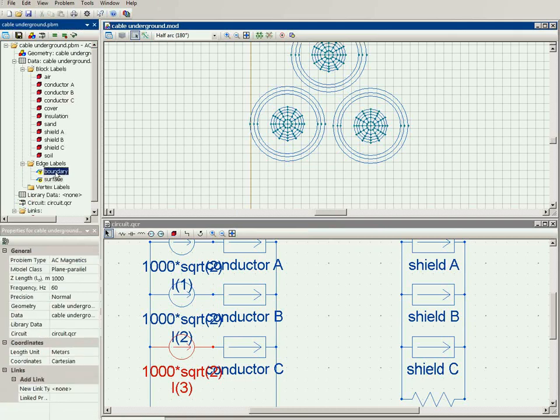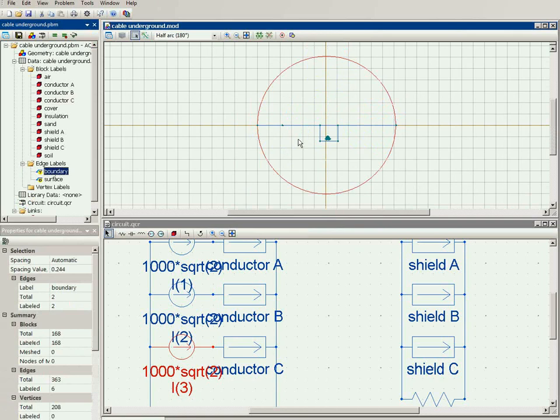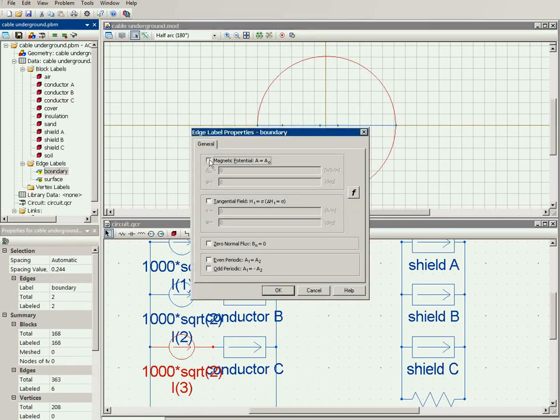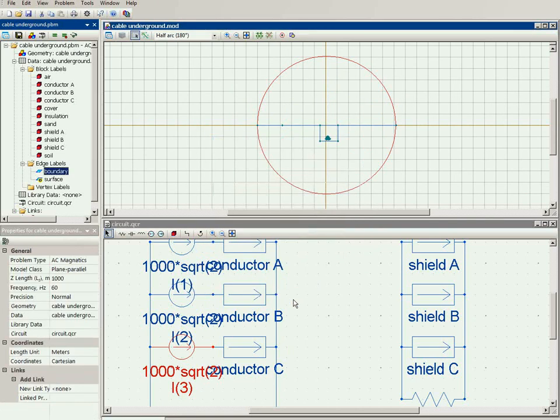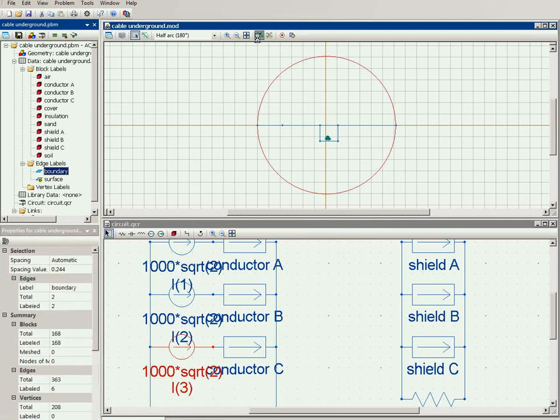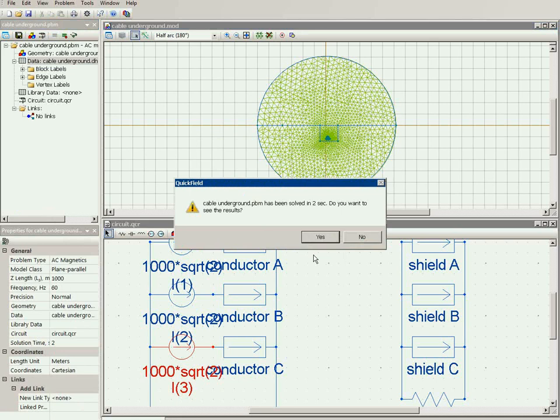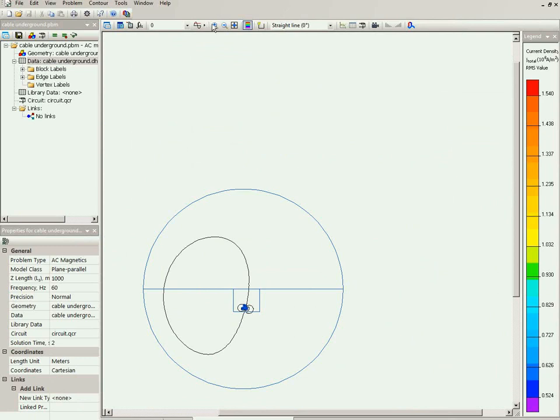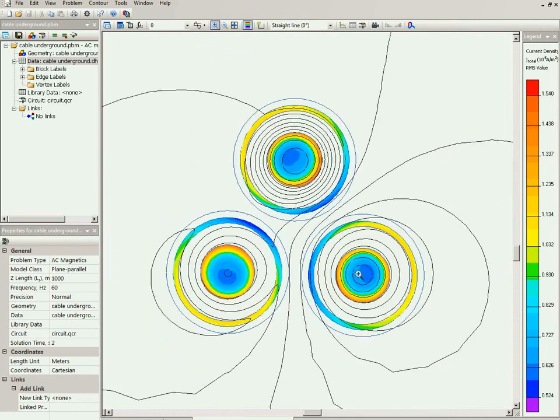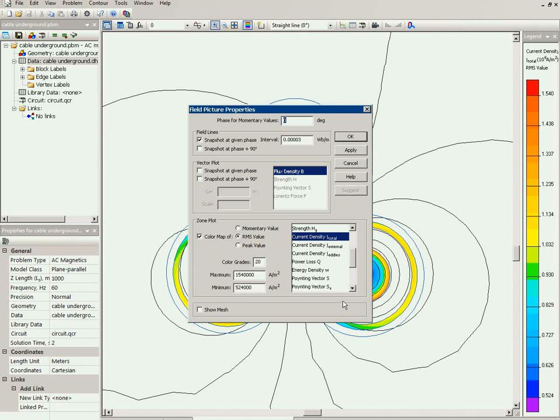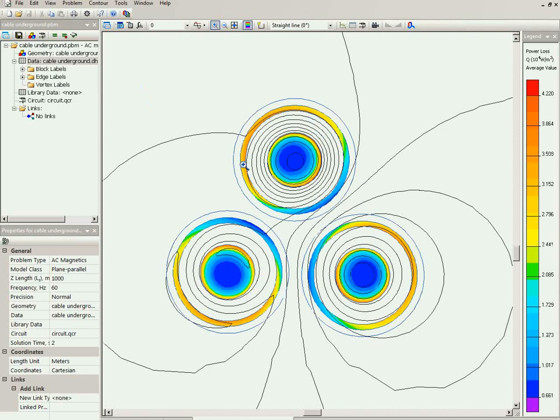The finite element model is ready. At the external boundary — far away from our cables where the electromagnetic field fades to zero — I specify a zero magnetic potential condition. Now I can run the simulation: I build the finite element mesh, save all problem files, and run the analysis. Here you can see the current density distribution in the central conductor and in the screens of the cable. The current density distribution is not uniform, and indeed the power losses distribution is not uniform either.